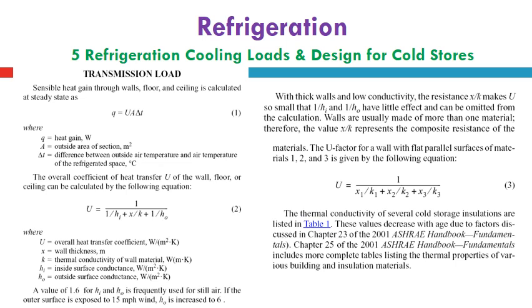per square meter Kelvin. With thick walls and low conductivity, the resistance X over K makes U so small that 1 over HI and 1 over HO have little effect and can be omitted from the calculation. So walls are usually made of more than one material. Therefore, the value X over K represents the composite resistance of the material.